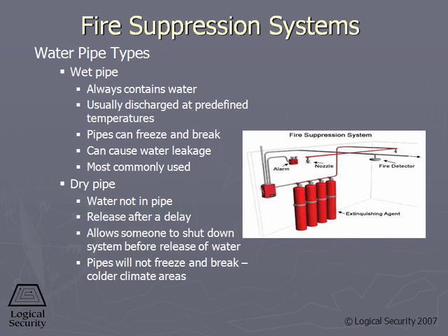So within the building itself, wet pipe is a very popular form of sprinkler system because the water is there already and it makes for a very fast reaction. The problem, though, again, occurs if the area is not thermally controlled, such as a garage or some other area like this, a warehouse. If these pipes freeze, the water expands and breaks the pipes, and we have water damage over the area. Again, the wet pipe is the most commonly used, and it's probably the least expensive.